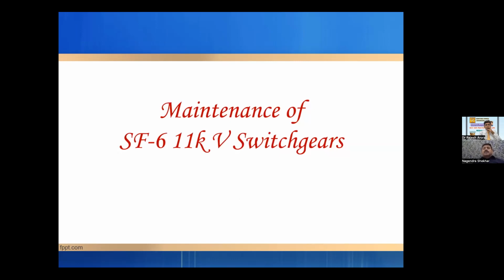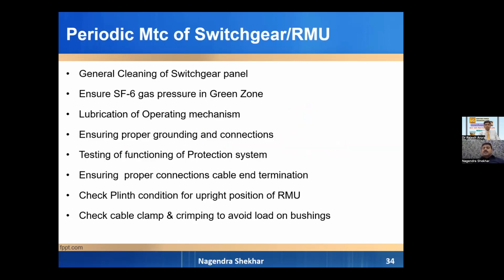The maintenance of SF6 11 kV switchgears. As BSES adopted these SF6 breakers, most of the switchgears which have completed their active life of 25 years, we have replaced with these SF6 breakers. We shortly call them RMU, ring main units. So periodic maintenance of these RMUs: cleaning of switchgear panels, ensuring the relays are clean so that they can be seen properly. The SF6 gas should be in a green zone.